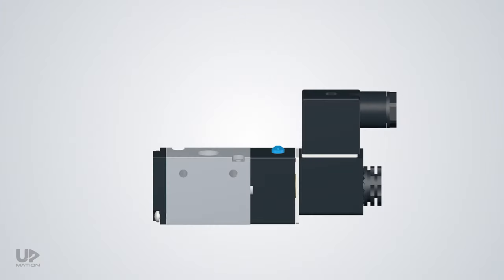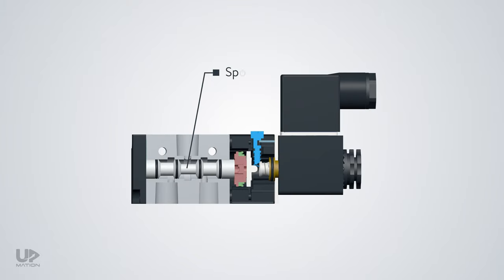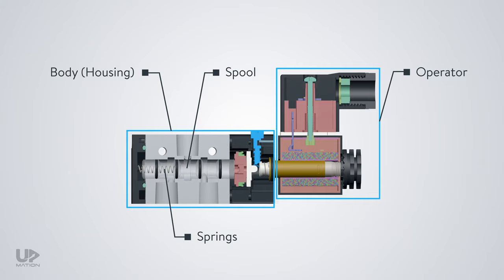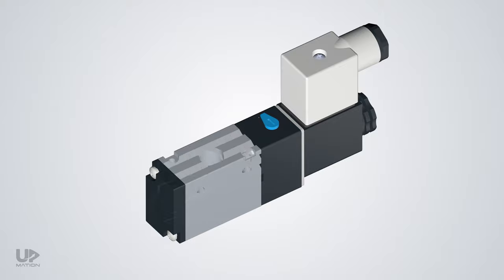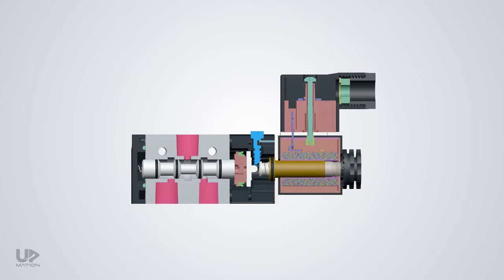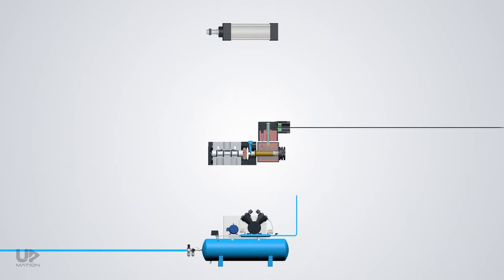The general components of a spool valve are like this. A spool, which is a cylindrical component. Operator, which we have talked about extensively in the previous video, and there might be more than one operator. Body or housing. And maybe springs on one or both ends. The spool moves within the bore of the housing. Some holes are machined on the body of the housing to open the fluid passages into or from the valve. These holes are known as ports and are connected to the other hydraulic or pneumatic circuit components.